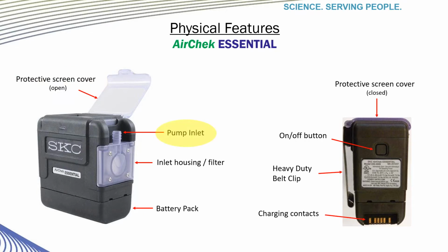The pump inlet fitting is recessed to help prevent breakage when the pump is dropped or hit against something during normal activities for the wearer. It also helps prevent kinking of the tubing when the wearer bends over or turns. The clear inlet housing makes it easy to see if the filter has become discolored and needs to be cleaned or replaced. The lower portion of the pump is the battery portion, which can be easily replaced in the field if necessary.